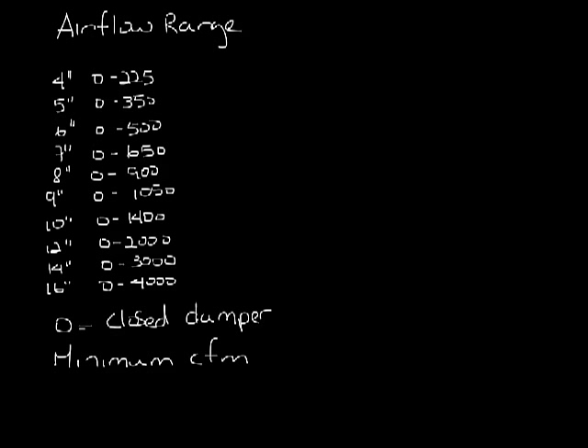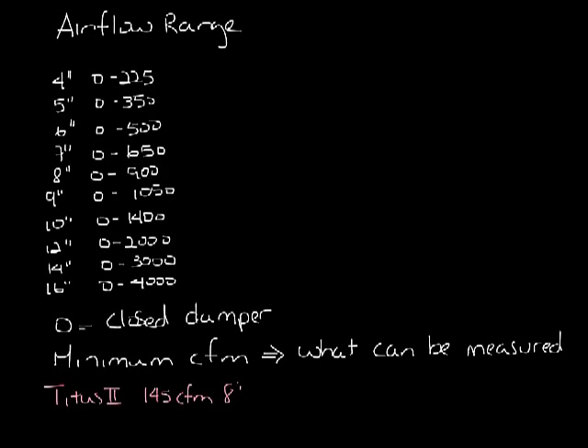Something to know about the minimum CFM of a VAV box is that it's all about what the VAV box controller can measure, not what the box itself can handle. For instance, our Titus 2 pneumatic controller can control down to 145 CFM on an 8-inch inlet, but the Titus 1 only goes down to 190 CFM.